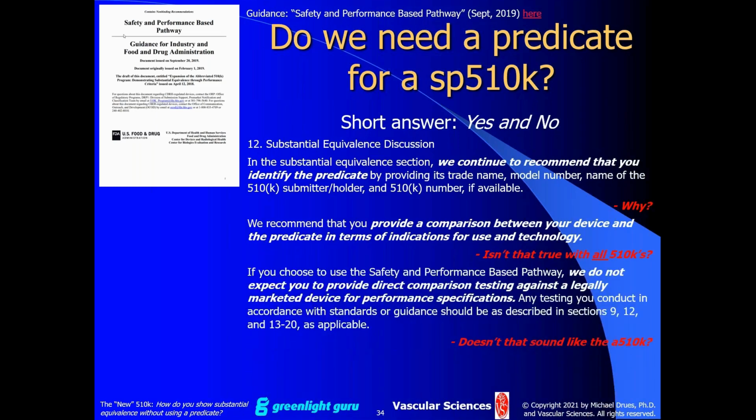Finally, FDA says, we do not expect you to provide a direct comparison of testing against a legally marketed device for performance specifications, because instead, we're going to be doing our testing to the standard. We're showing that our device meets the standard. And this is why I say that the SP 510K is very, very similar to, if not substantially equivalent to, the abbreviated 510K, because that is exactly the idea of the abbreviated 510K.